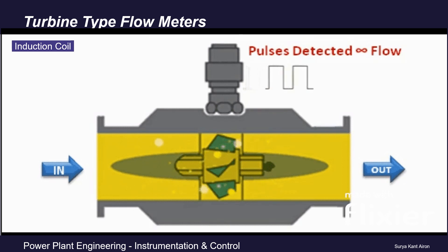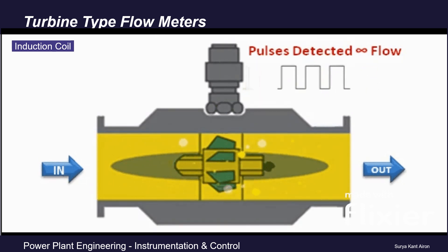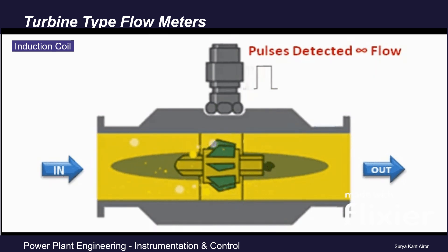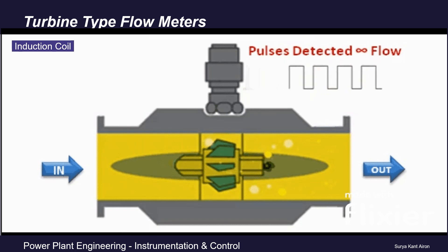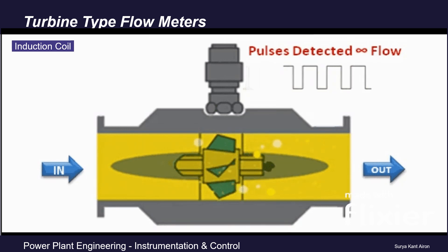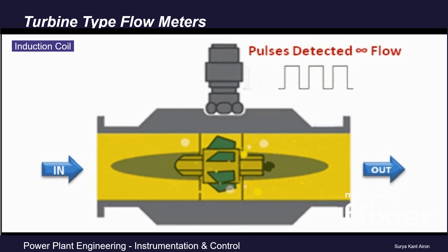Electrical components consist of a pickup sensor system. It has either an induction coil, a Hall sensor, or a photoelectric cell. These sensors transmit signals to a signal transmitter, which is further connected to DCS or PLC. An induction coil generates electrical impulses in direct proportion to rotor speed and transfers them to a recording device.